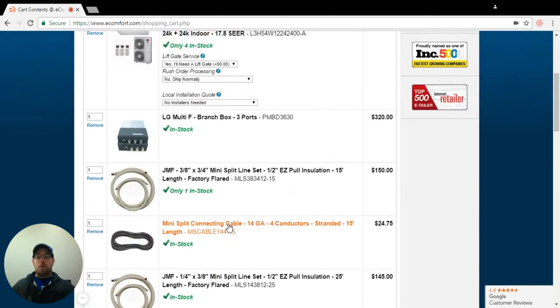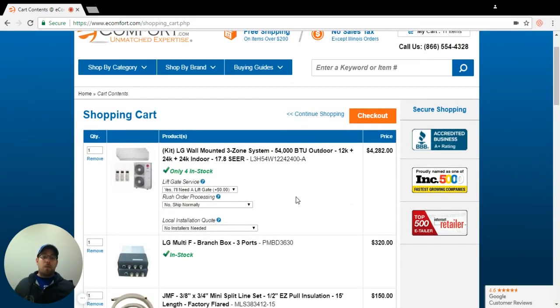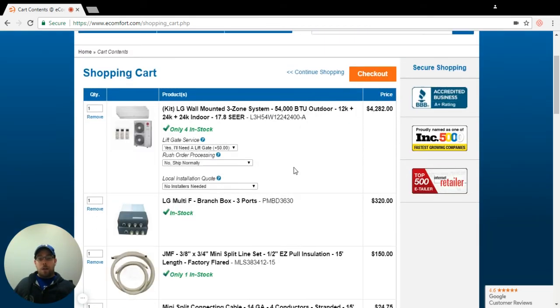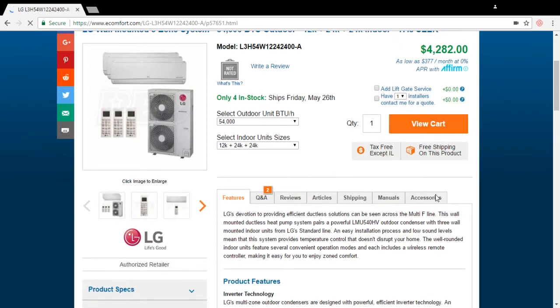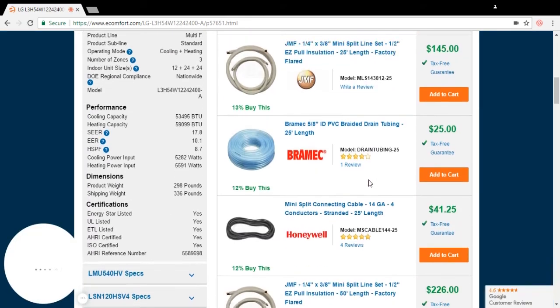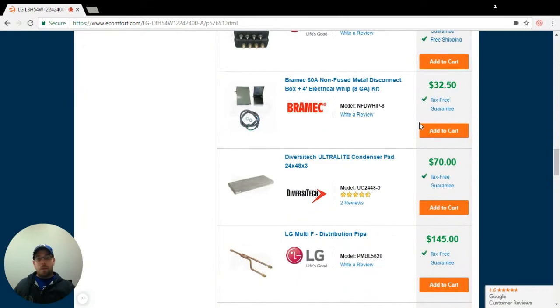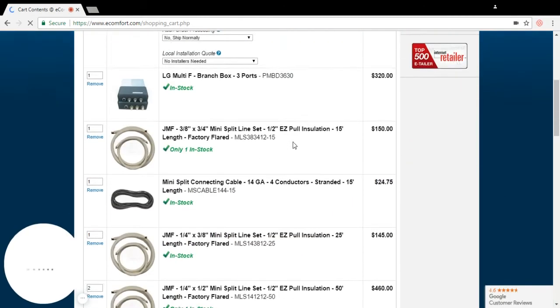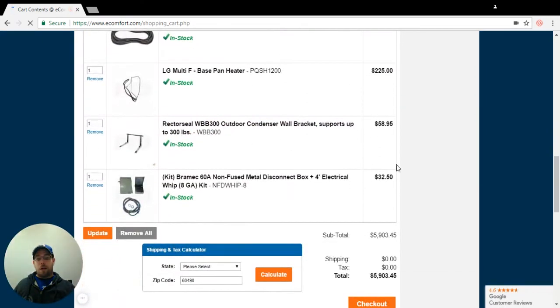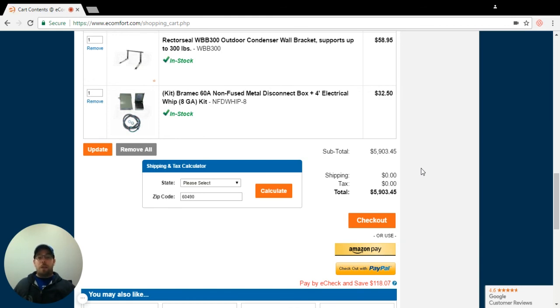There may be other components that are required for installation. You can purchase some of those other items locally like breaker sizes, wire between the breaker panel to the disconnect box. And actually that reminds me, I need a disconnect whip for this. Let's pull up the disconnecting whip. There we go. We're looking at an eight gauge because it is a larger condenser. Now I have all the components I need. If you have any questions, always feel free to call in or send an email. We're definitely here to help. Have a wonderful day.